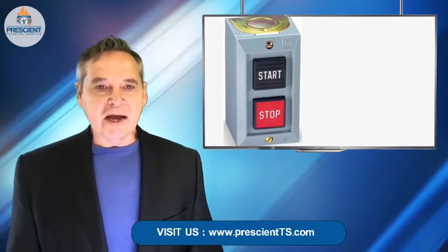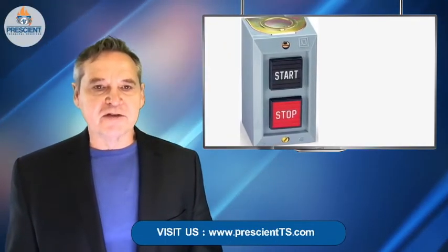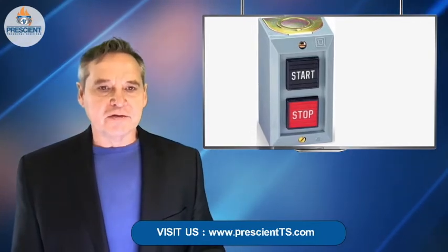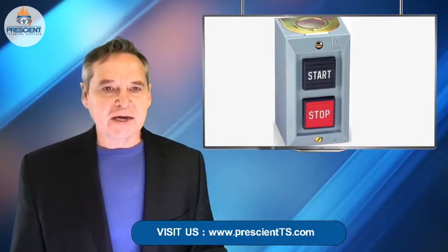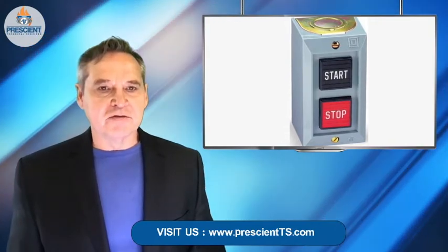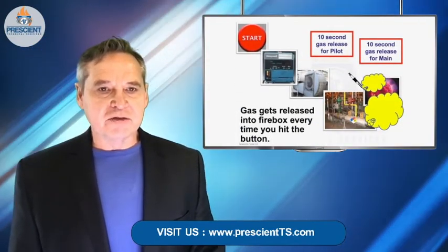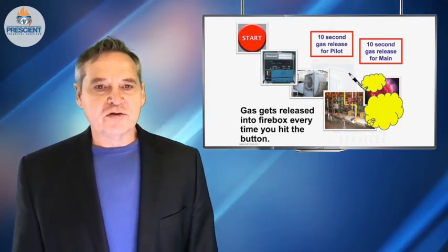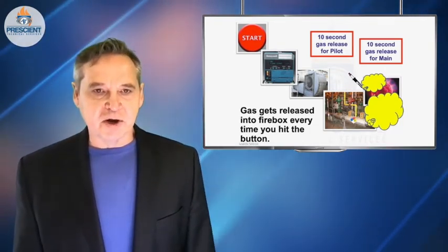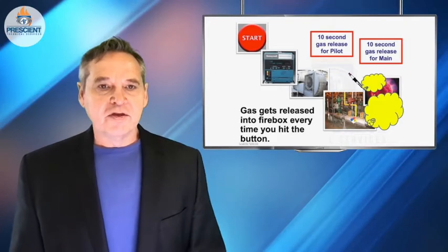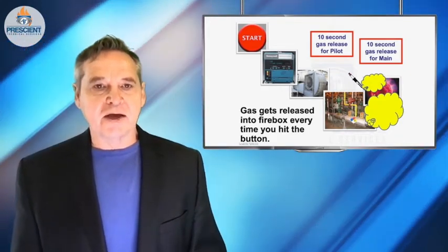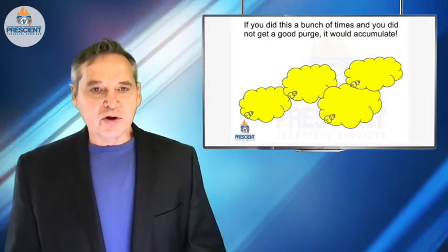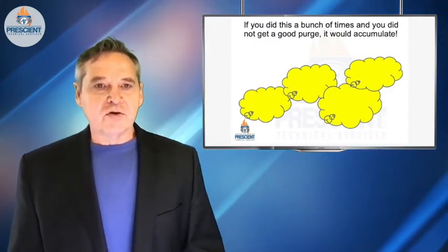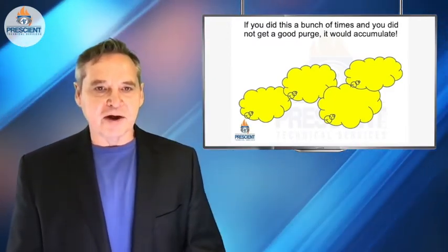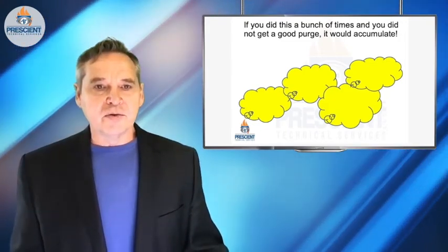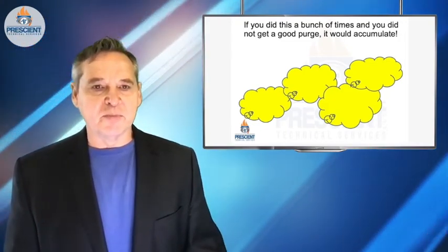To really understand the hazard that I'm speaking about here when you're trying to light something off, you need to understand some basics. Like what actually happens? What are the events that are set into motion when you actually touch that start button? You should know that every time you initiate a light-off process, there's fuel released. This happens when we try to light a pilot and when we try to light the main flame. If your purge is not effective, you'll keep accumulating fuel in the firebox along with air till you ultimately get to some type of a flammable mixture.